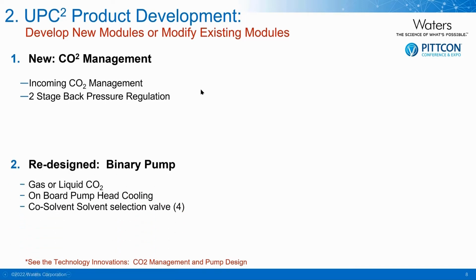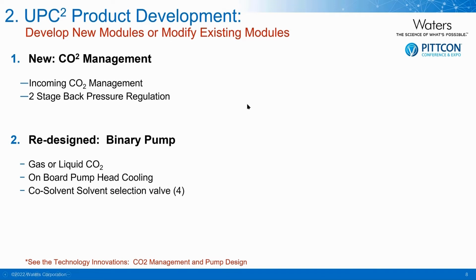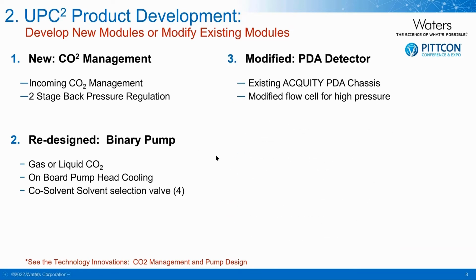We also had to redesign the binary pump, requiring gas or liquid CO2 handling, onboard pump head cooling, and a co-solvent solvent select valve. We made a slight modification to the PDA detector to allow for a higher flow cell for higher back pressures, as well as modifications to reduce noise from CO2.